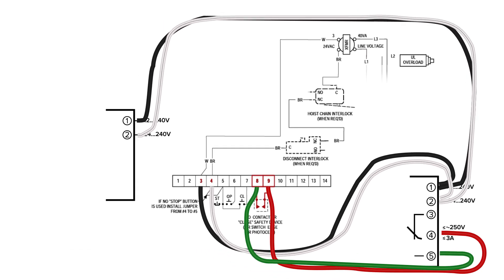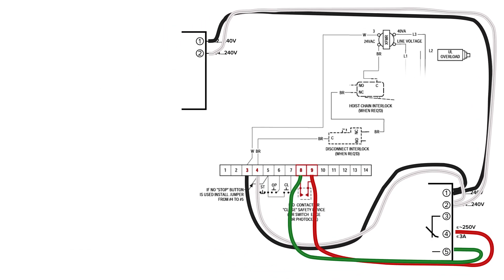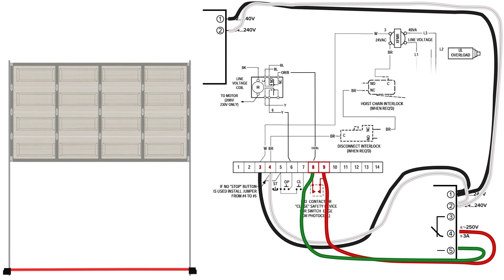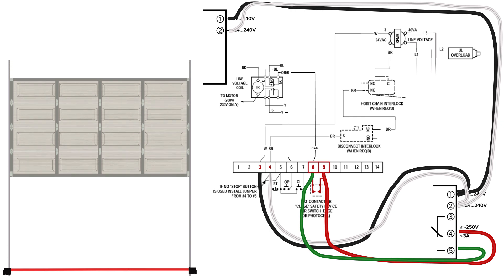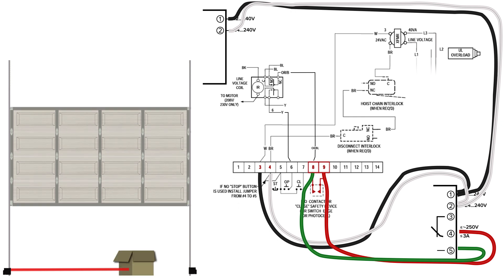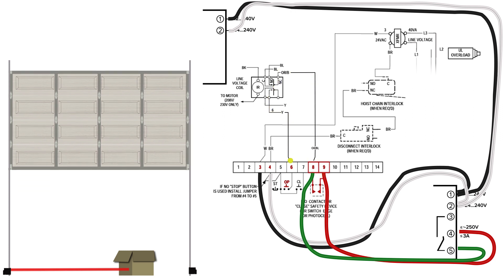Here's how this system works in operation. The eyes are aligned allowing the door to close. When the beam is interrupted the contact switch is flipped. A signal is sent from the receiver up to the operator through terminal 8 up to the motor control telling the operator to open the door.